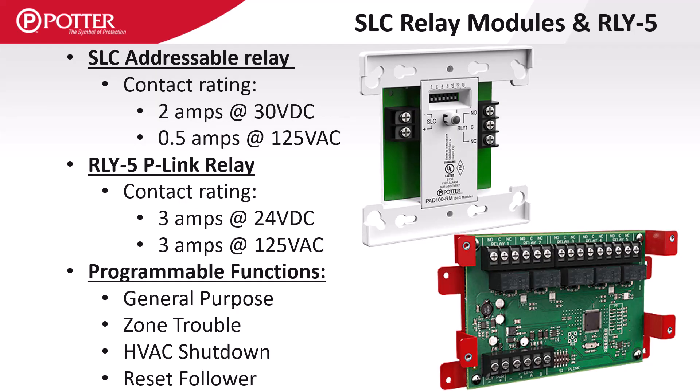Potter addressable relays have several available functions. Those functions include General Purpose, where the relay changes state on alarm; Zone Trouble, where the relay changes when a trouble condition exists within the zone; HVAC Shutdown, which is used in conjunction with the input type HVAC Restart to meet New York City requirements that HVAC units be restarted manually; and Reset Follower, where the relay only changes state during the panel's reset cycle.